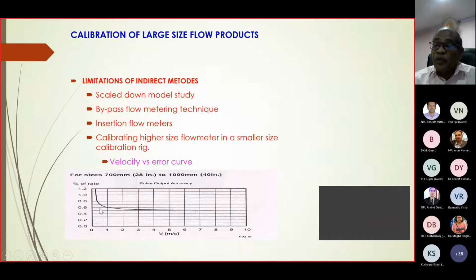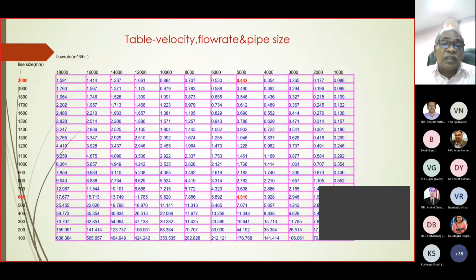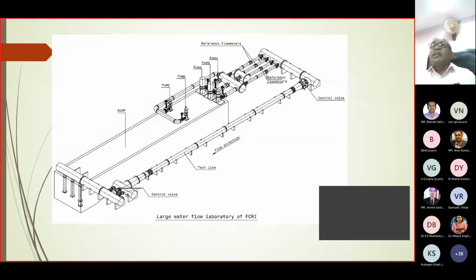So normally, if you are using a smaller size lab for calibrating higher size flow products, you are calibrating at an inaccuracy level. So keeping all those things in mind, the indirect methods are not so good. So we have made a facility in India, that is in FCRI, which can cater up to a line size of say 2000 mm diameter. So this is the large water flow laboratory.